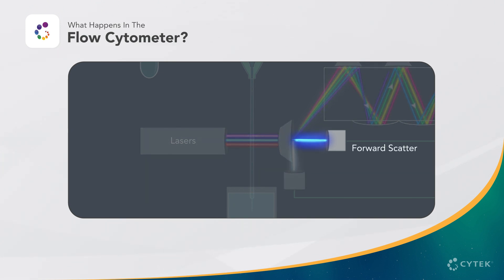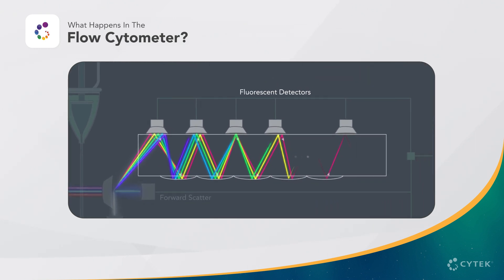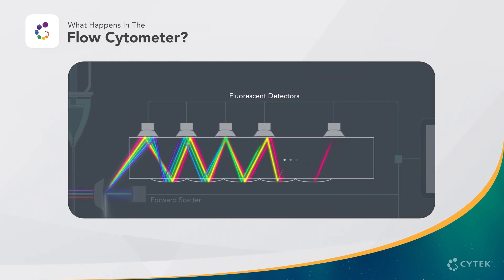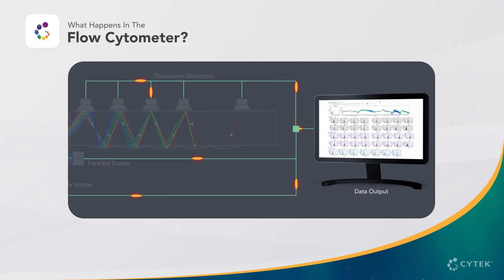Forward scatter is the measurement of laser light scattered by the cell in the forward direction, and is correlated with cell size. Side scatter is a measurement of laser light scattered at a 90 degree angle, and provides insights into the granularity or complexity of cells. The light emitted from the fluorophores are directed to fluorescent detectors, with the number and arrangement depending on the cytometer configuration. Photons are then converted to electronic signals and processed into data, which is displayed in real-time within data plots and saved to an FCS file for subsequent analysis.